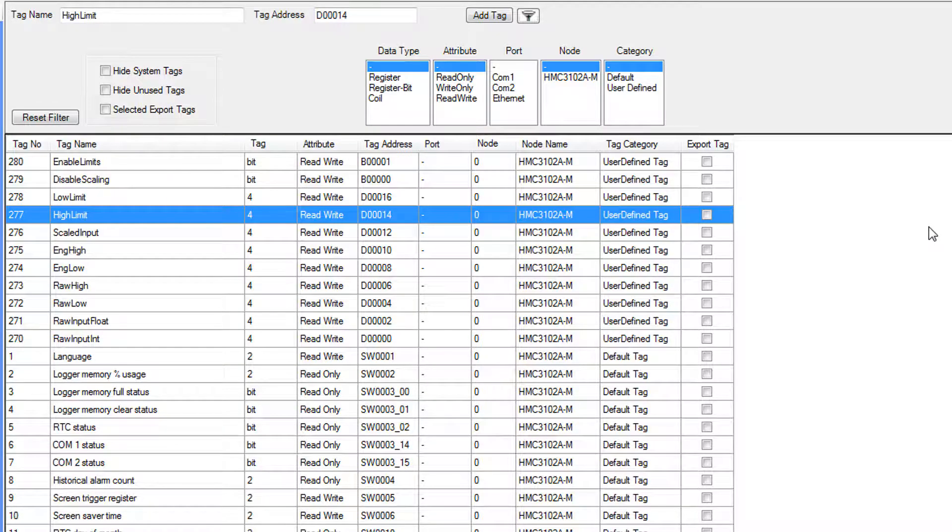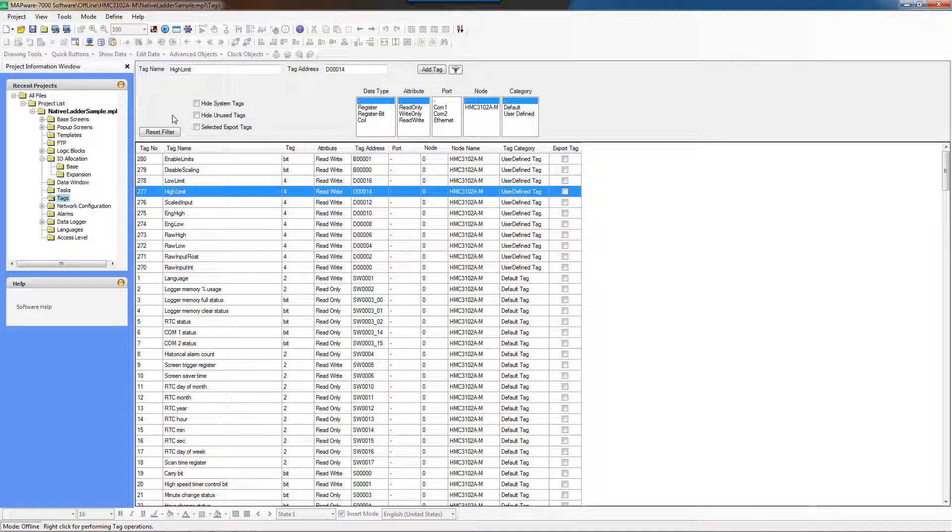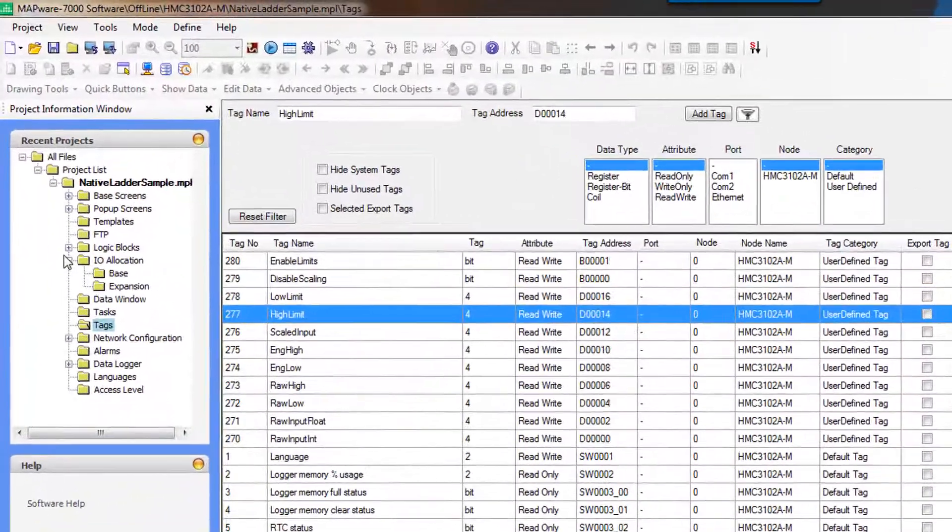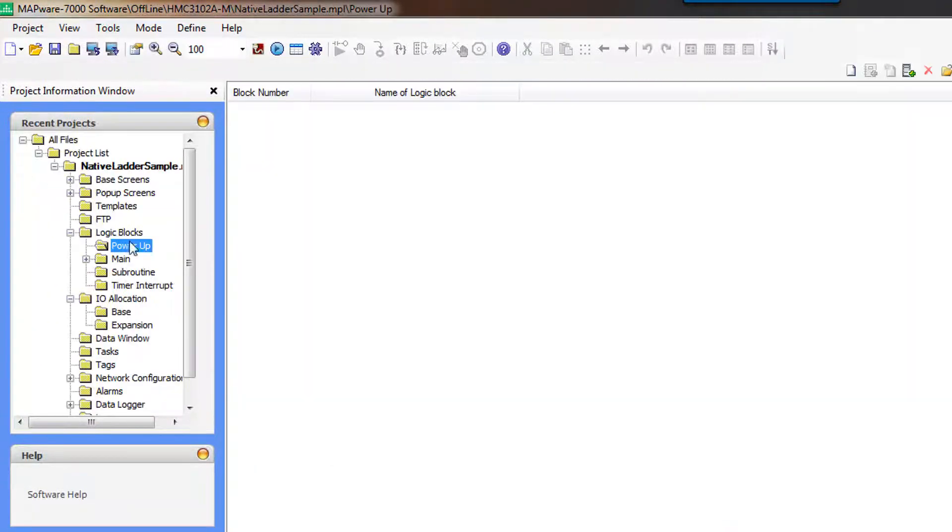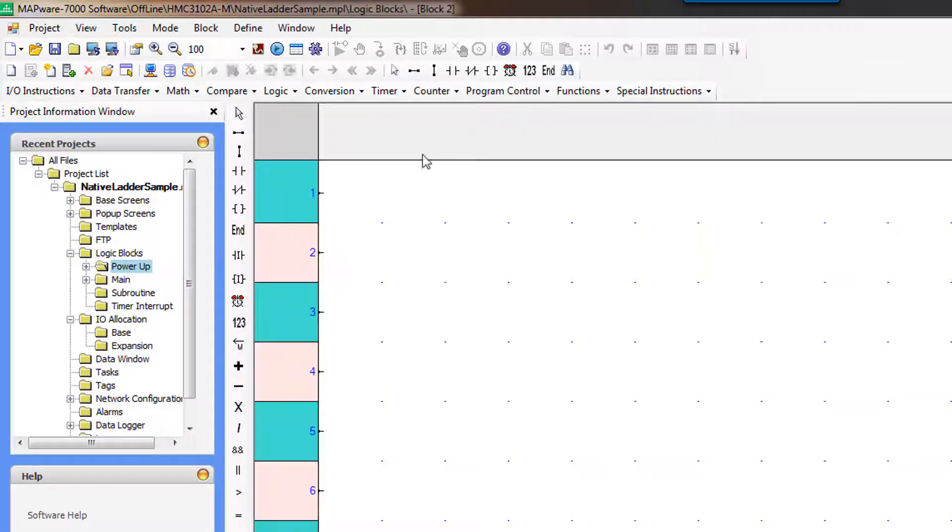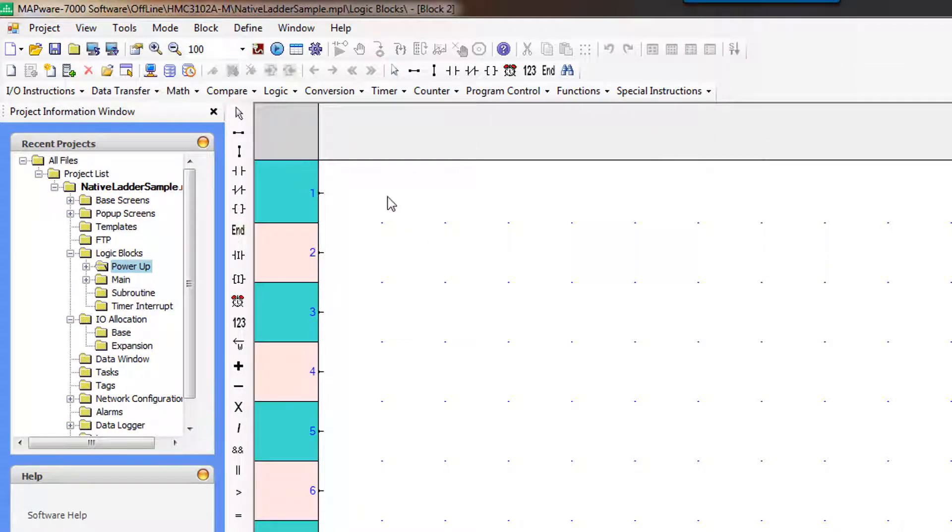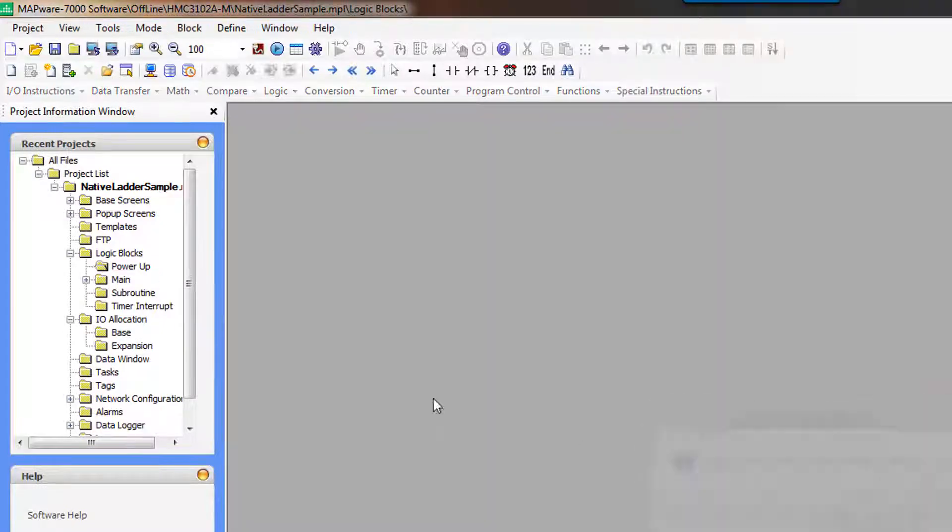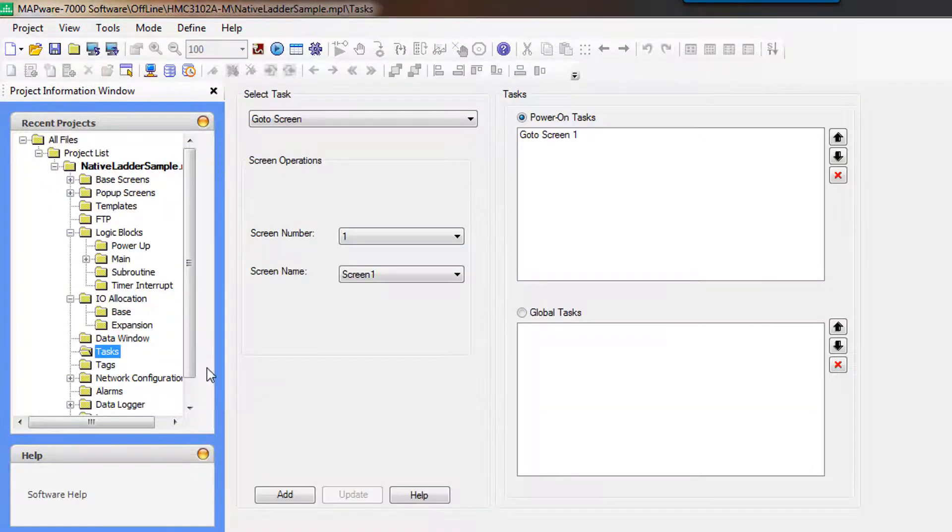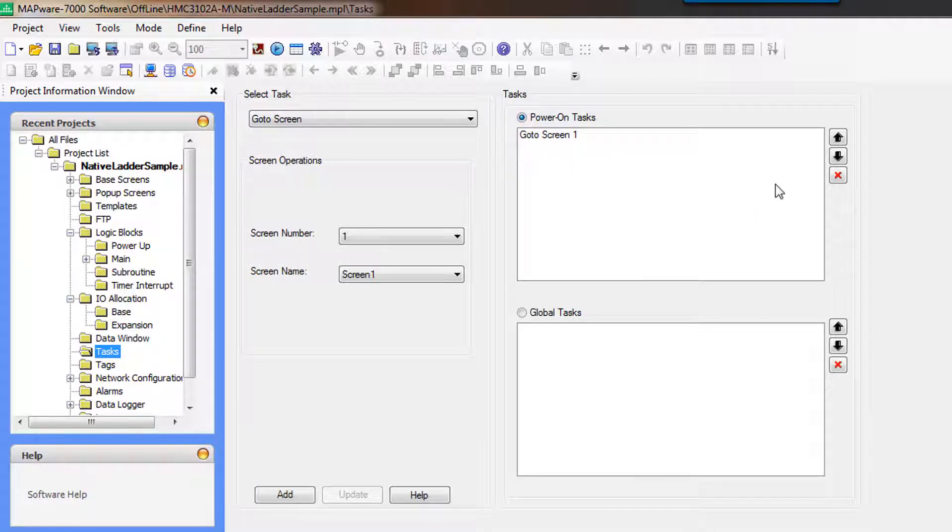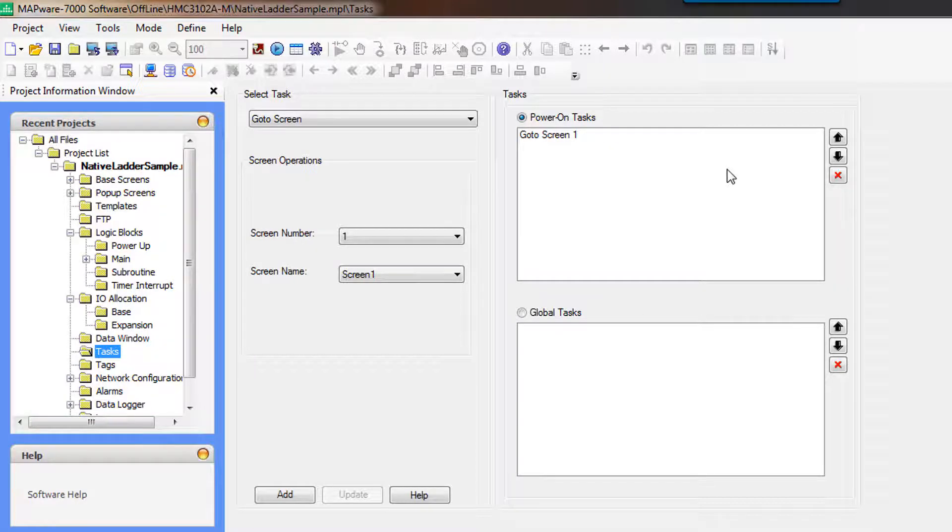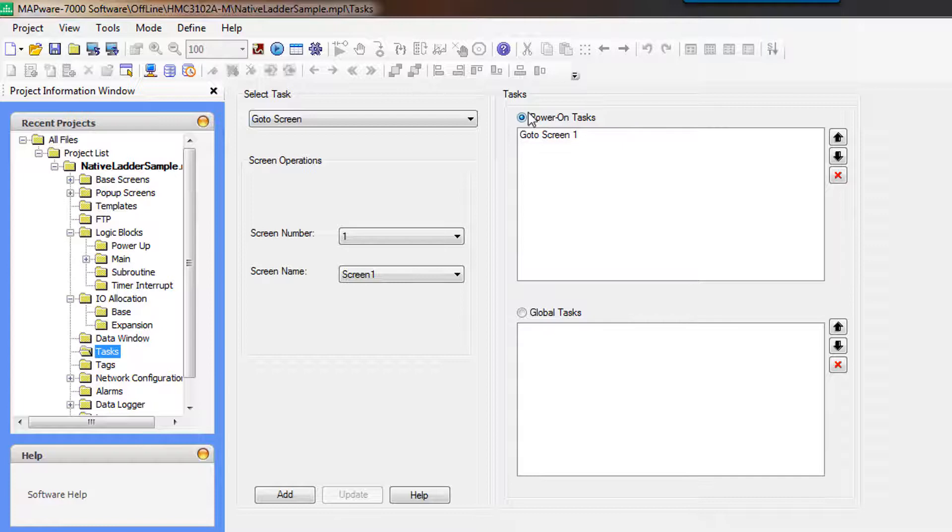And so now that we have defined some tags, we're going to initialize them. There are two locations that you can initialize tasks or functions or tags. The first is within a logic block. You can create a powerup logic block. And this piece of logic will only run once at powerup. I'm going to delete that because we don't actually want that. We're going to do it in a task. And so there are poweron tasks that are, again, run just once at startup when the unit first powers on and then never run again. You can also create global tasks that will happen continuously. So we're going to create some poweron tasks to initialize some variables.